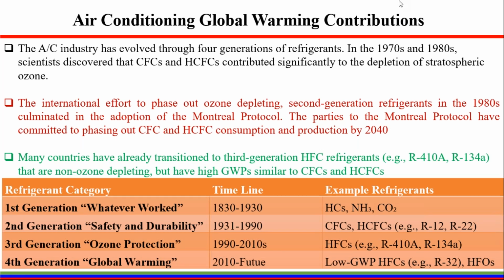In the table below, I have shown the first generation, second generation, third generation, and fourth generation air conditioning refrigerants. We can go directly to the first generation refrigerants. It shows that what was used between 1830 and 1930 includes hydrocarbons, NH3 and carbon dioxide. Then the second generation, between 1931 and 1990: CFCs and HCFCs that include R12 and R22. And the third generation, when ozone protection was there, and hydrofluorocarbons are used. And the fourth generation, global warming, which is our future, with hydrofluorocarbons and hydrofluoroolefins.